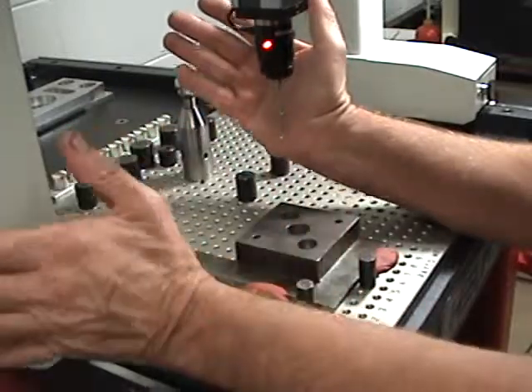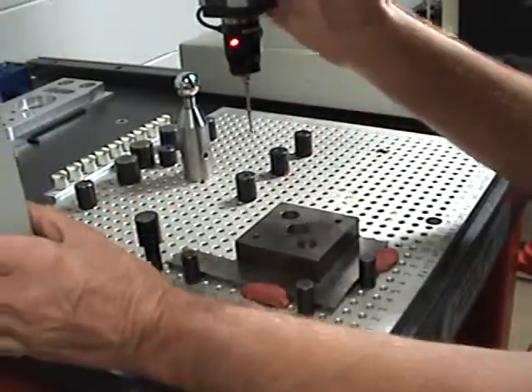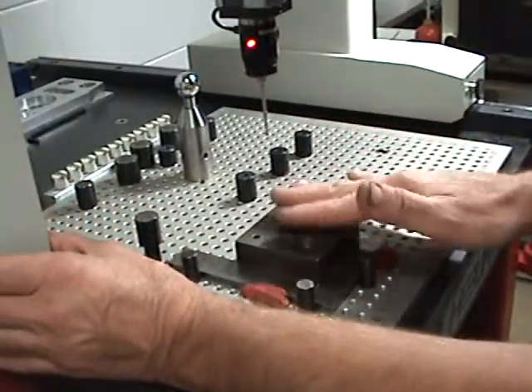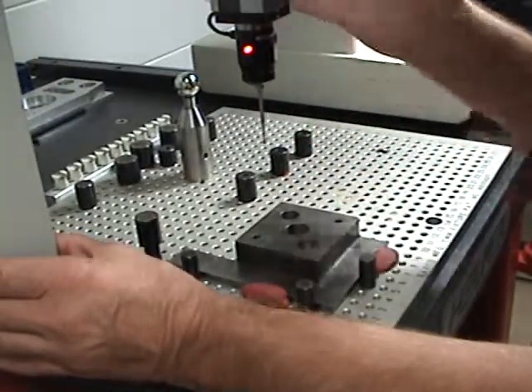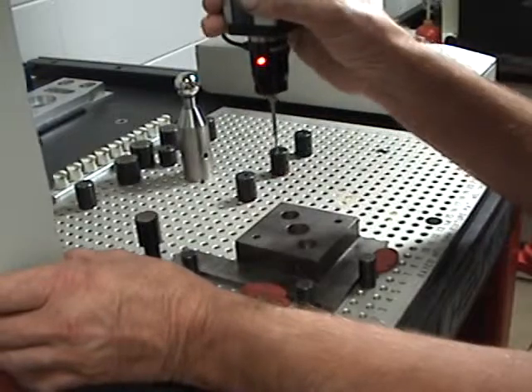I want to show you how to hold the probe and how to lean on the machine. We're going to hold the y-axis arm here and touch some points on this part, which you'll be measuring. It's pretty critical that everything is nice and smooth.